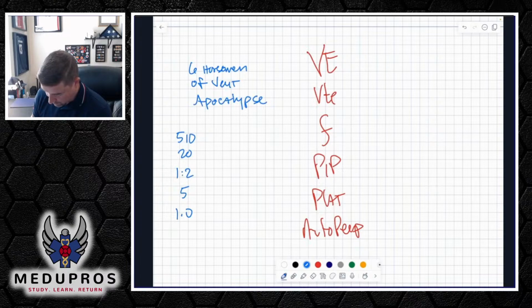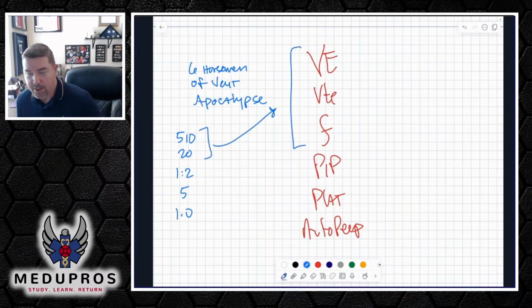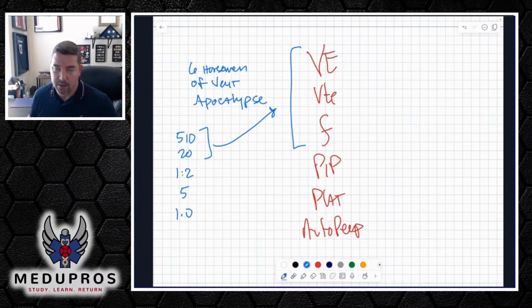All right. So what we want to do is make sure that these settings closely match the actual measured data that the vent sends us. Otherwise, we need to make some tweaks right now, because where we are is we just essentially put them on the vent, came up with the initial settings, and now we're getting this real-time data.